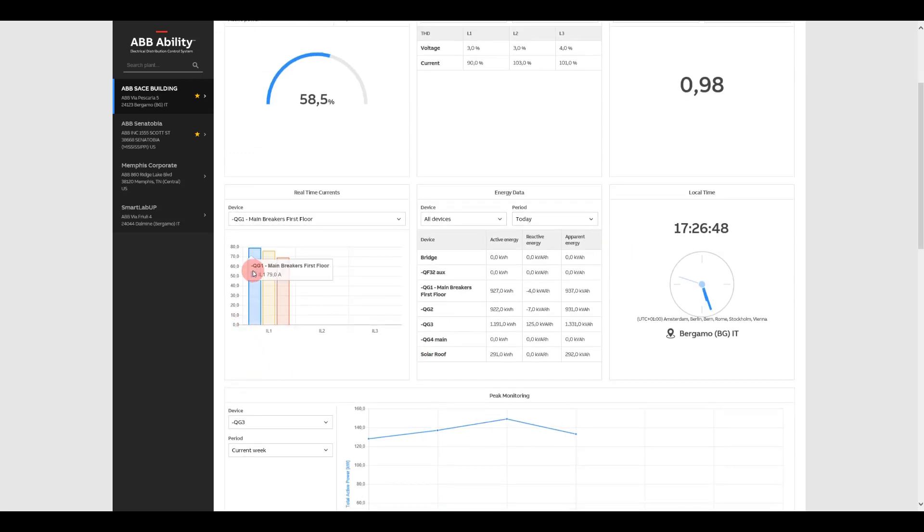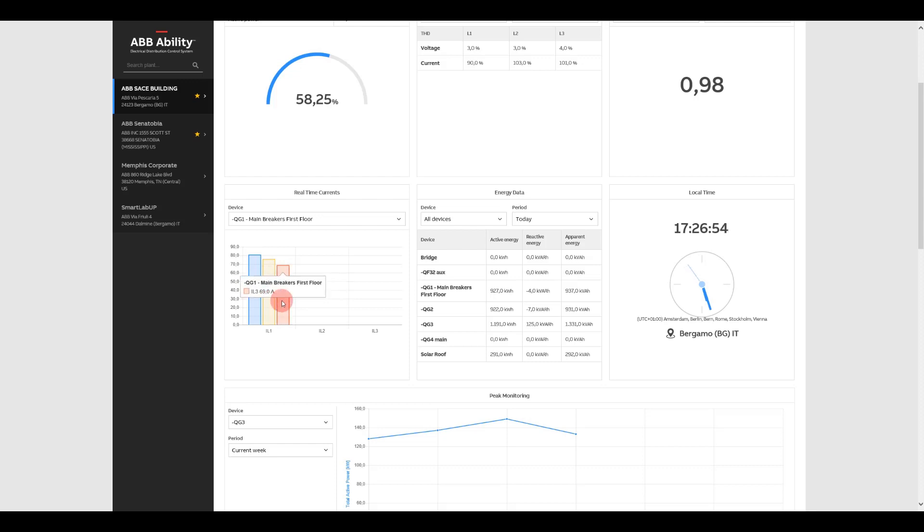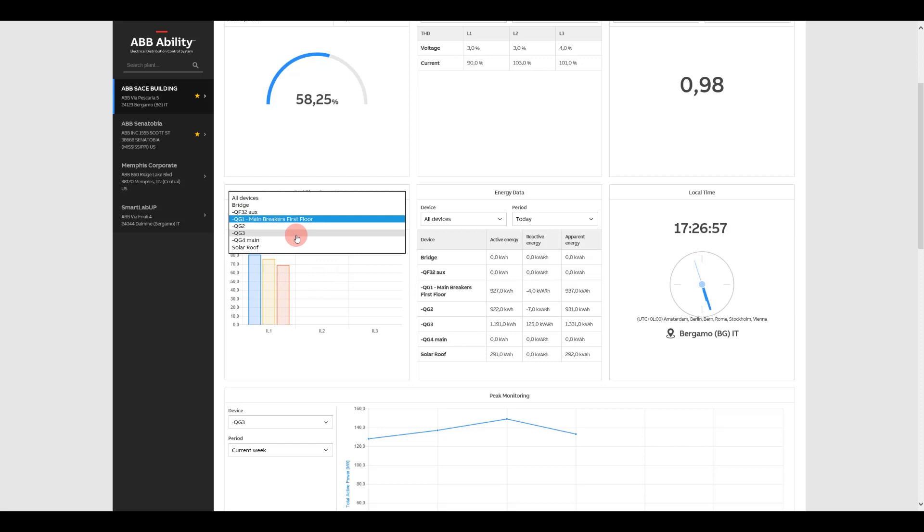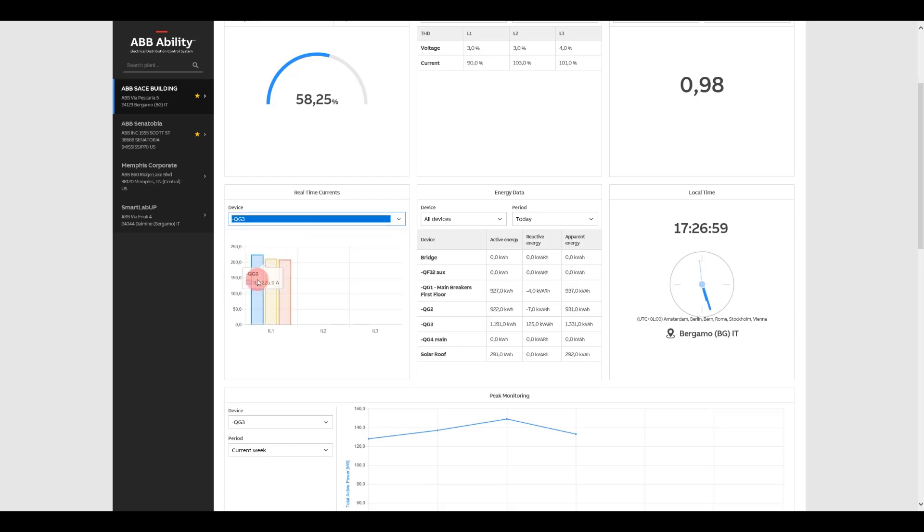Real-time current lets you look at each phase so you can identify a phase imbalance or potential downstream issues like bad lugs, a bad connection or oxidation. High current could indicate an issue with a motor or other piece of equipment, a poor connection or just heavier than normal usage.